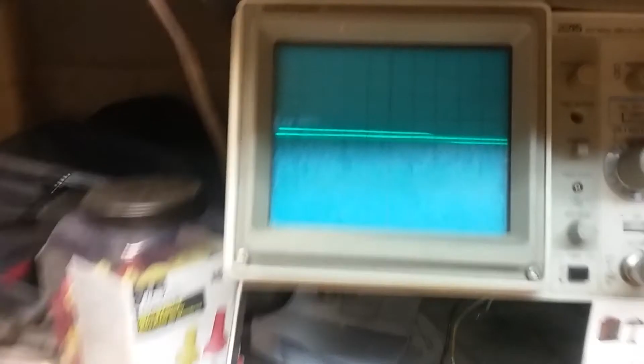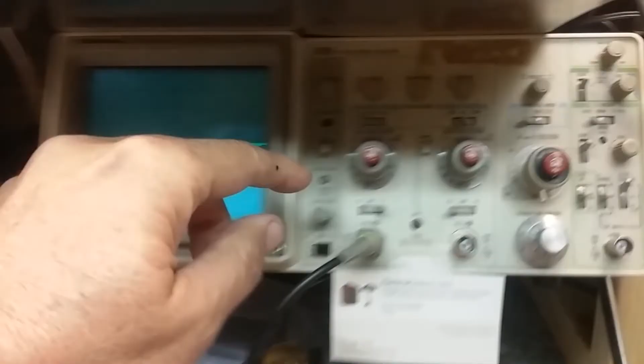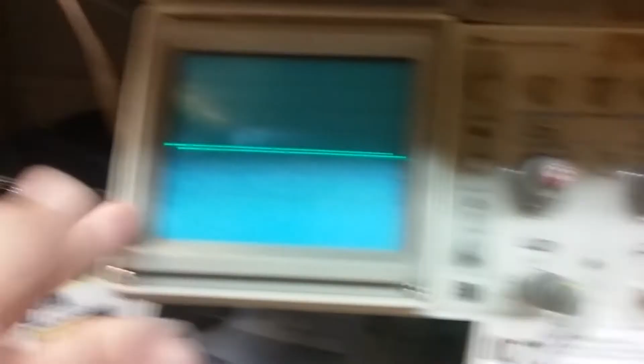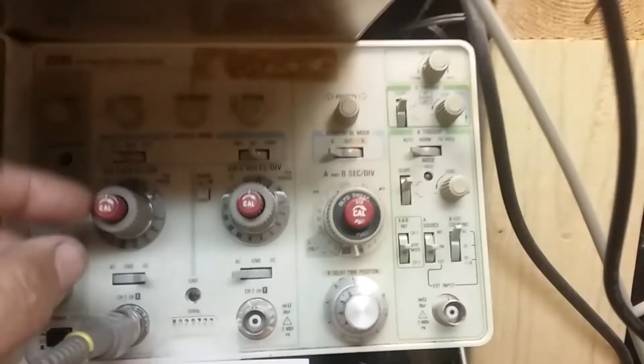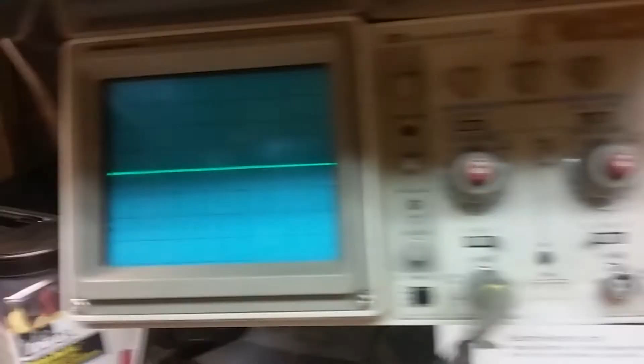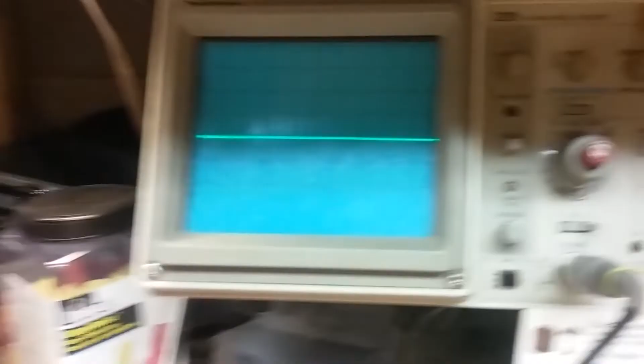So I have a power, and I'm on 0 there, and you see it's zeroed out. If I raise the volts per division to 20, then as I crank this up, you see it go up a whole lot faster. Right there, we're up to 3 divisions, 60 volts. I'm showing 63 volts DC.